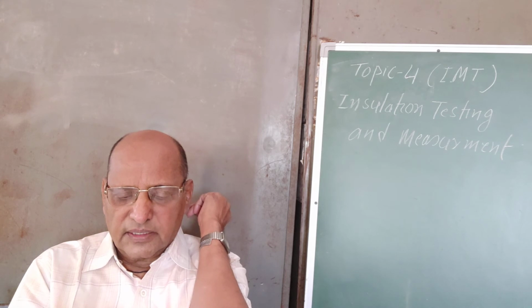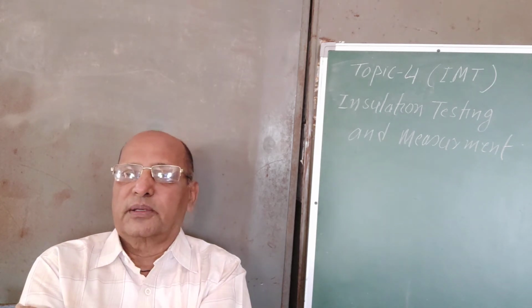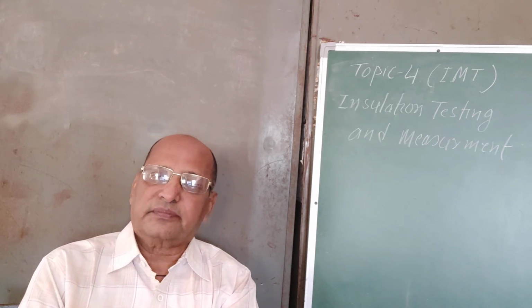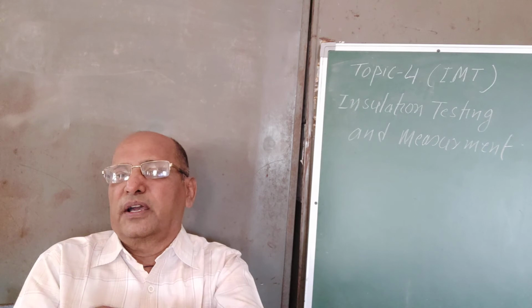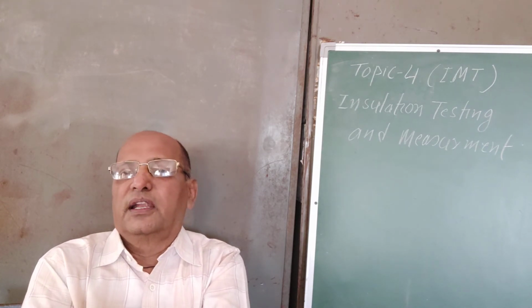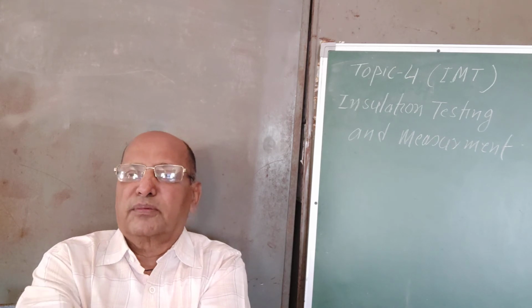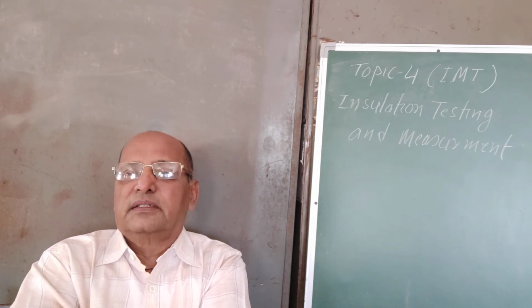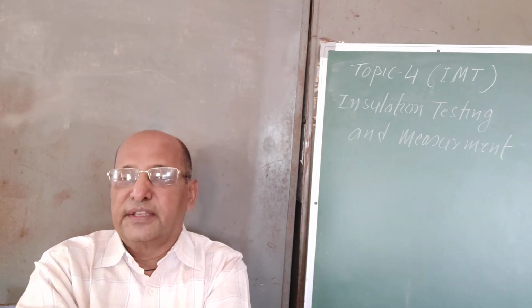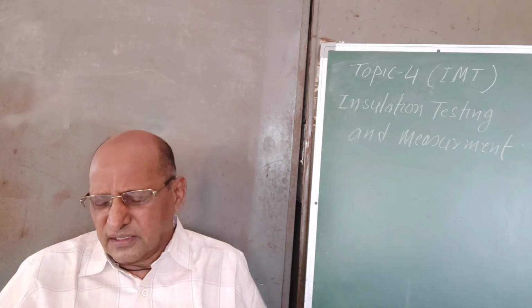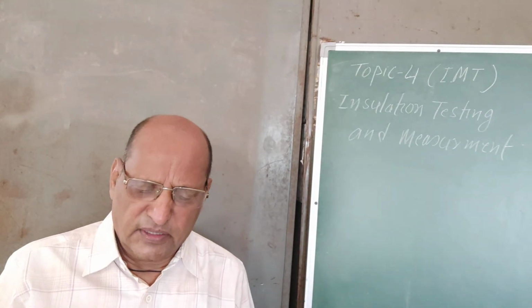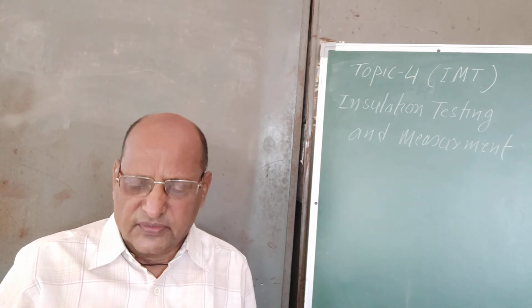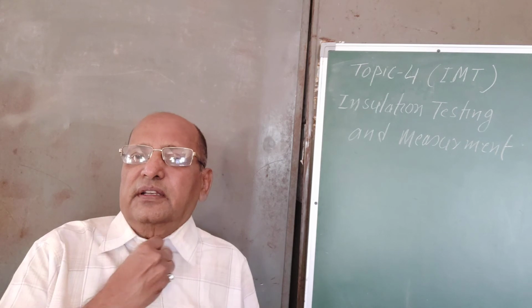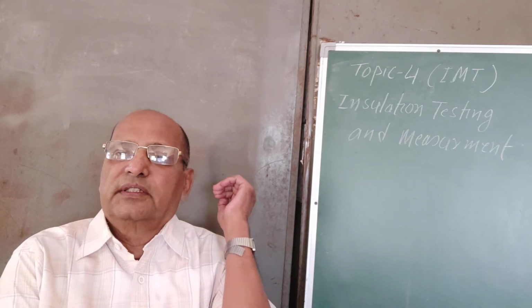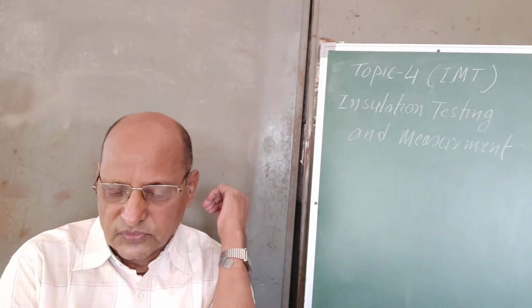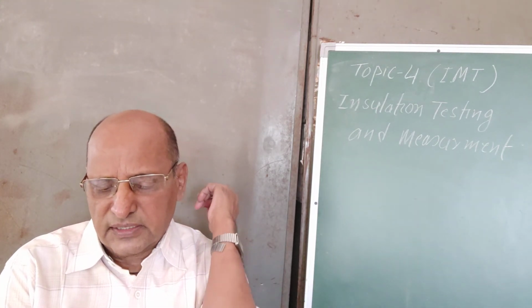Then measurement of internal temperature of winding, as I have told you, has 2 types of arrangement. One is for power transformers, where a pyrometer or infrared thermometers are used, and for distribution transformers mercury thermometers are used, which are installed near the conservator tank. So a direct reading can be taken from that. Temperature gauges are also used. They are a mechanical type of arrangement based on metal expansion with temperature, calibrated in degrees centigrade. So in that case we also use the temperature gauge for that purpose. So these are all things I have discussed.